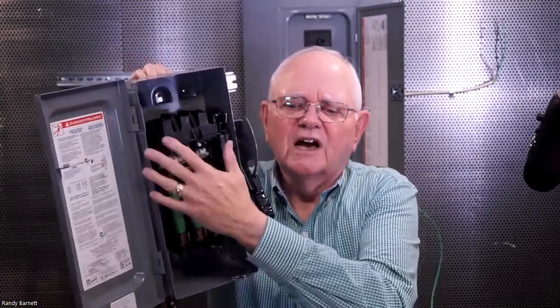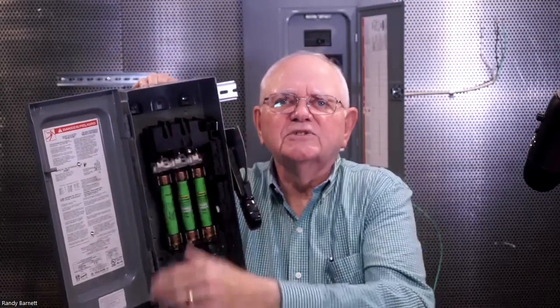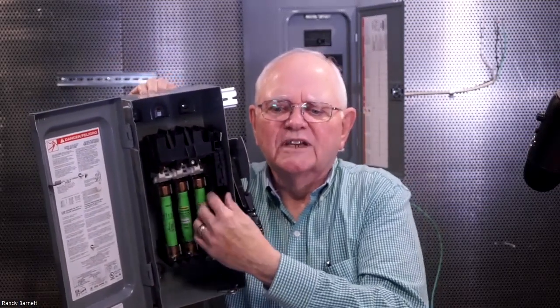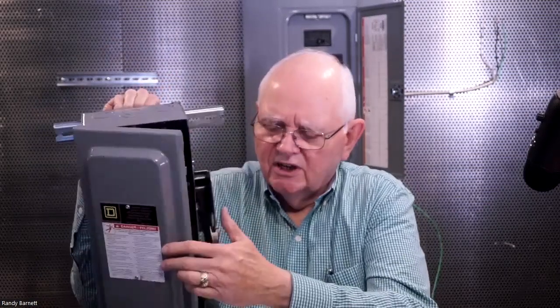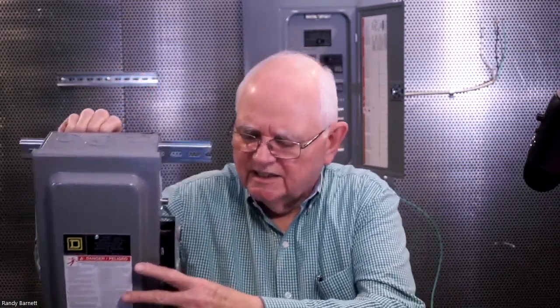You have to make sure everything operates properly. You go inside, and you may have to clean some stabs and contacts. Make sure all the parts are secure, the terminations are secure, and so forth. Some pretty standard cleaning and lubrication, whether you use a non-conductive or conductive lubricant on certain parts. As for electrical testing, you may have to test contact resistance, test for ground faults, and do insulation resistance testing. On these disconnecting switches, not so much, on a safety switch like this. But think of other types of switches that are covered in the code as well.